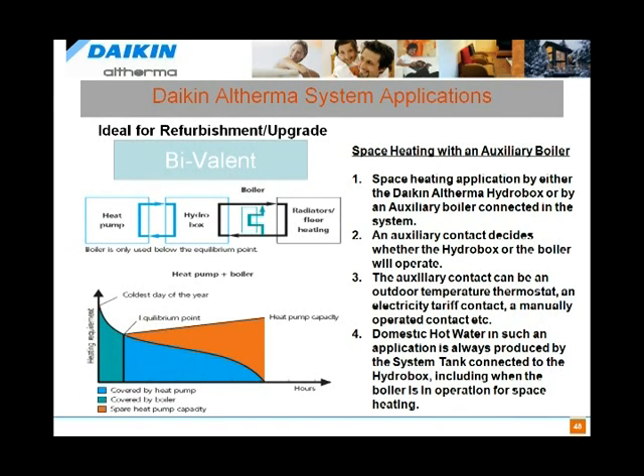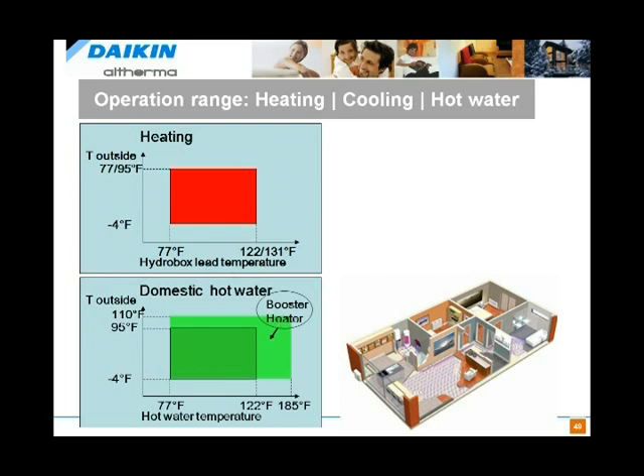They also have what's referred to as a bivalent system. There are marketplaces where you'll have an existing, let's say, propane boiler, and you want to just leave that in place for peak requirements and put a heat pump in to handle the vast majority of the load. There are also built-in contactors and devices for switching between heat sources if that becomes an interesting option, a dual fuel type of approach. This is very popular in the very cold environments where this is used in Europe. The vast majority is used in latitudes that are above 48 in Europe.